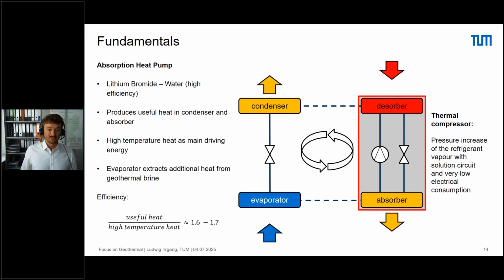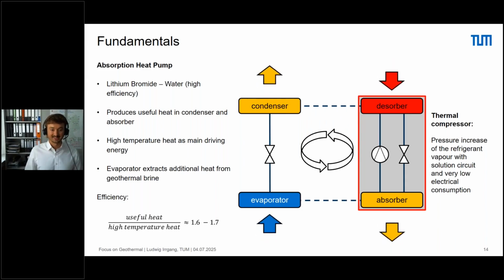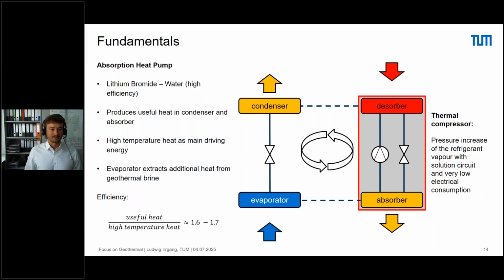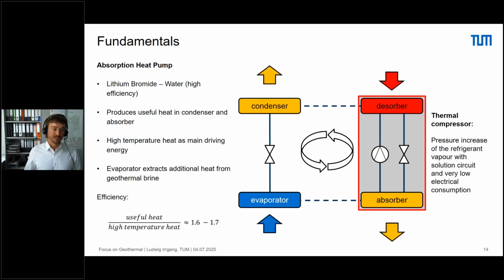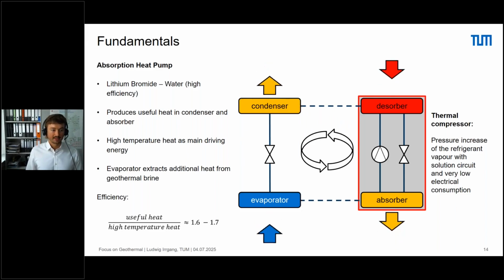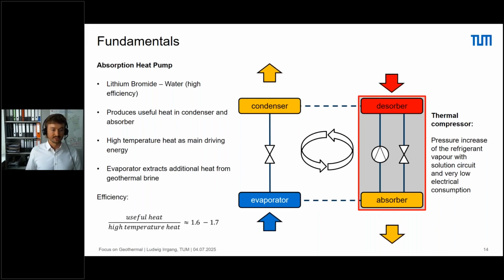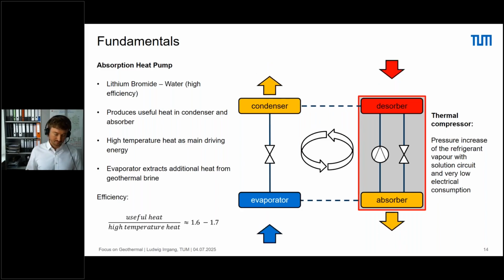The absorption heat pump, on the other hand, looks very similar to the absorption chiller. It's essentially the same cycle. The difference is that we use the condenser and the absorber heat output as the useful heat fluxes. And since the temperatures are generally higher in this cycle, we will use even higher temperature heat as the main driving energy. And the nice thing now about the heat pump is that we can extract additional heat from the geothermal brine just before reinjection with the evaporator. The efficiency is calculated with the useful heat at condenser and absorber in relation to high temperature heat input, and is usually around 1.6 to 1.7.